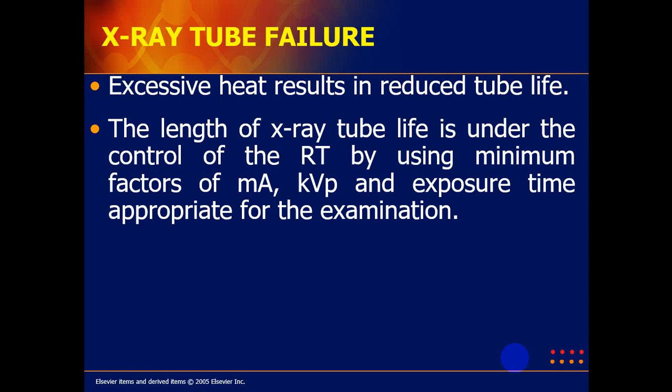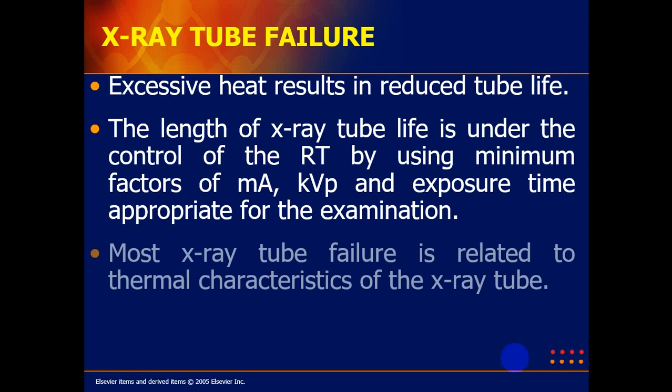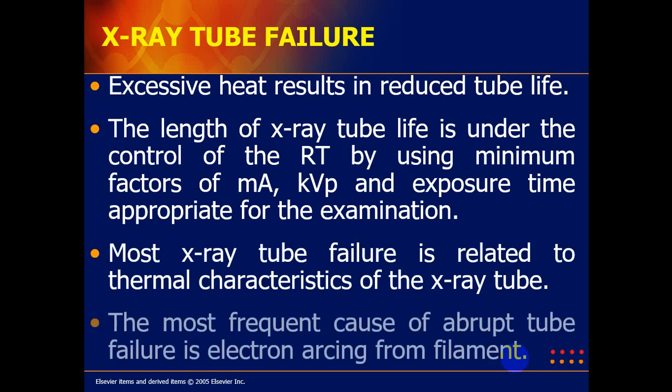So this is the remedy to preserve the X-ray tube life: using the minimum factors of mA, kVp, and exposure time appropriate for the examination. Most X-ray tube failure is related to the thermal characteristics of the X-ray tube.